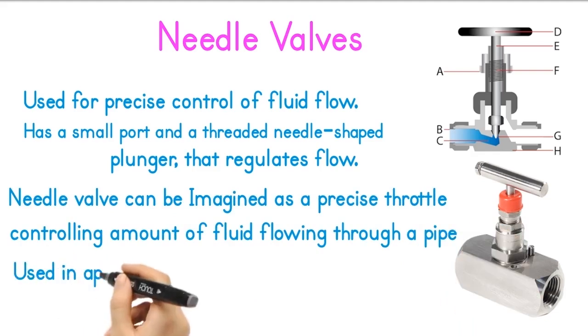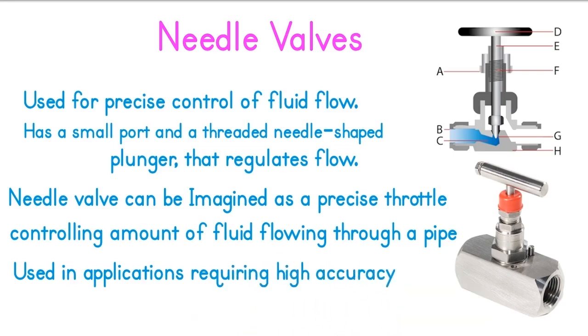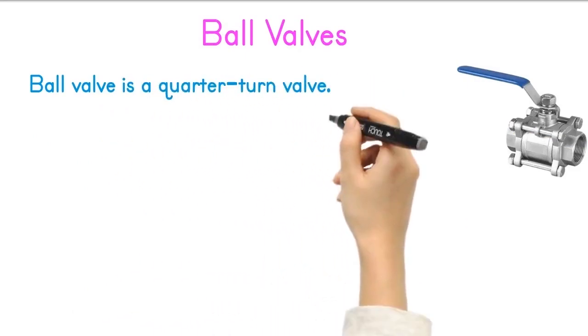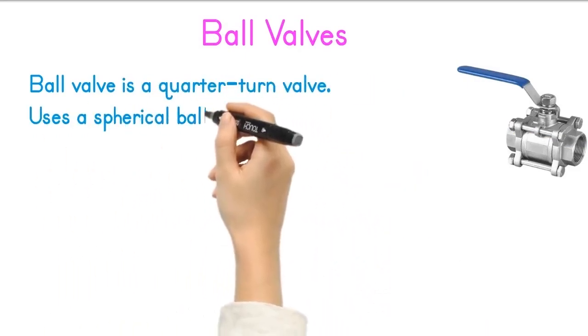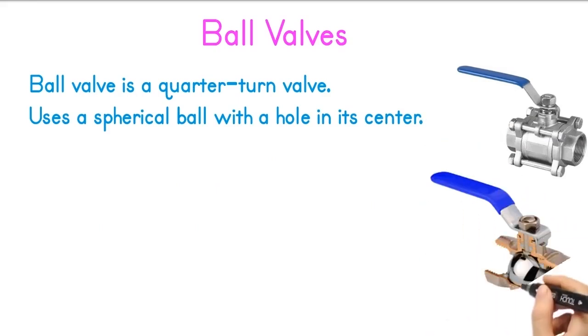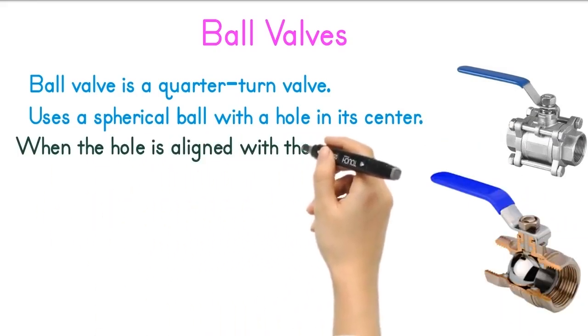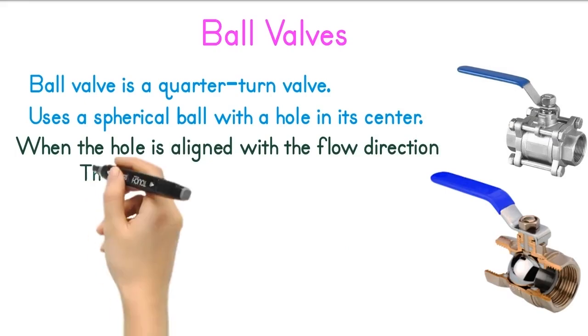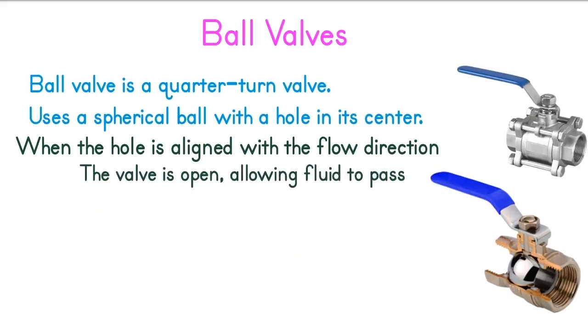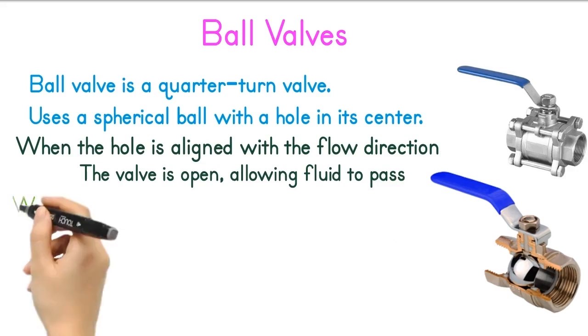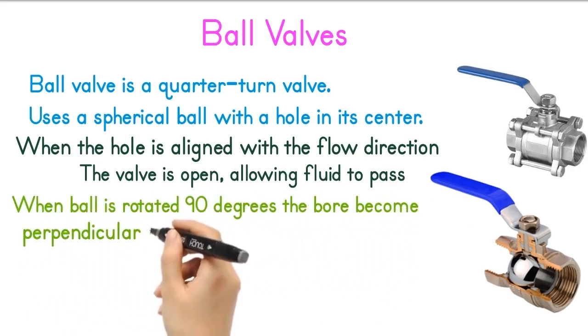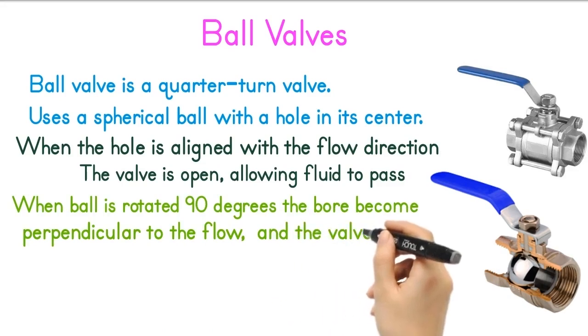Needle valves are often used in applications requiring high accuracy. Ball valves. A ball valve is a quarter-turn valve that uses a spherical ball with a hole, called a port, through its center to control the flow of liquids. When the hole is aligned with the flow direction, the valve is open, allowing fluid to pass. When the ball is rotated 90 degrees, it becomes perpendicular to the flow and the valve is closed.